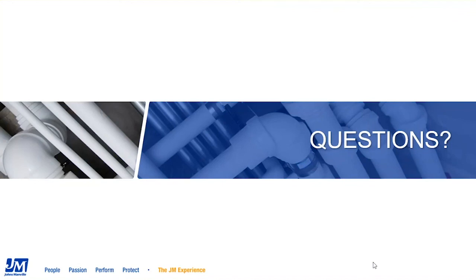All right, the next question again is for you, Meredith, and that is, how come HP plain does not meet the GreenGuard like the HP jacketed products? So when you install the pipe sections with the jacketing, because those sections are sealed, it meets the requirements for GreenGuard Gold, and when that pipe section is left exposed without any jacketing on it, it would not meet the certification.